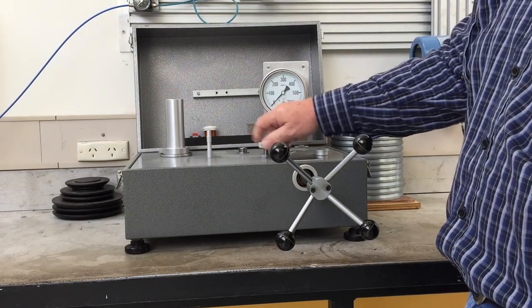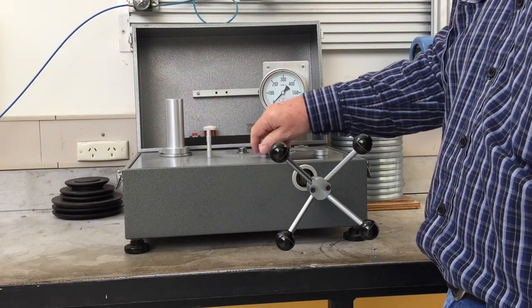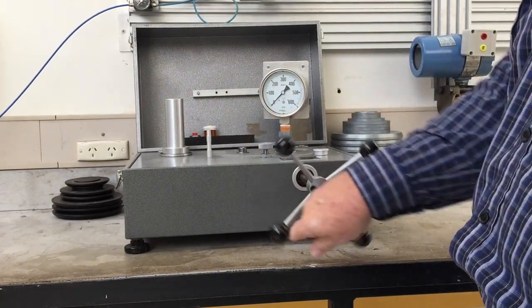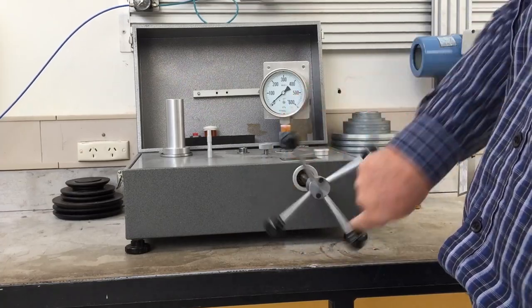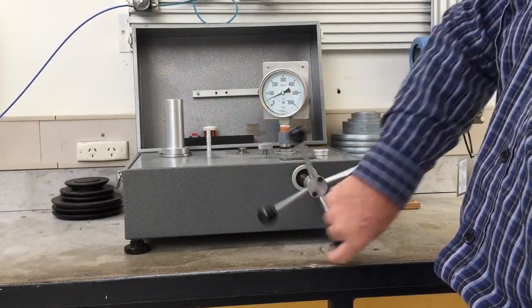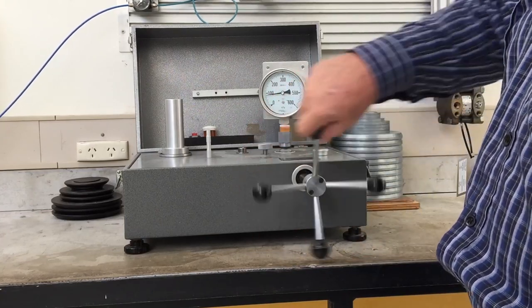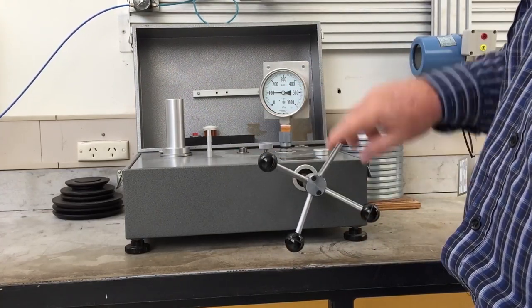Close the vent to start using the dead weight tester. Weights can be applied to the piston to increase the pressure reading. This dead weight tester has a minimum weight of the piston equivalent to 100 kPa.